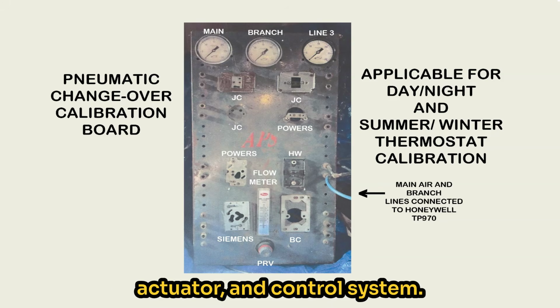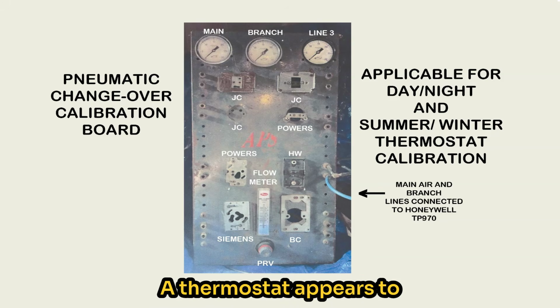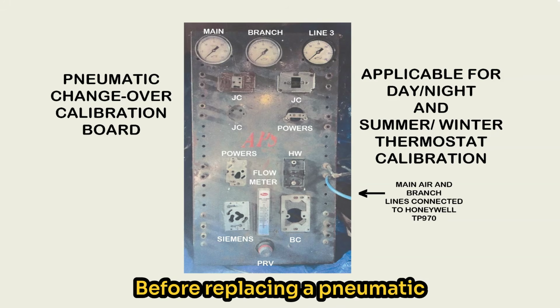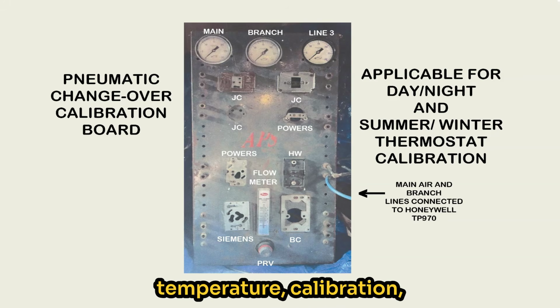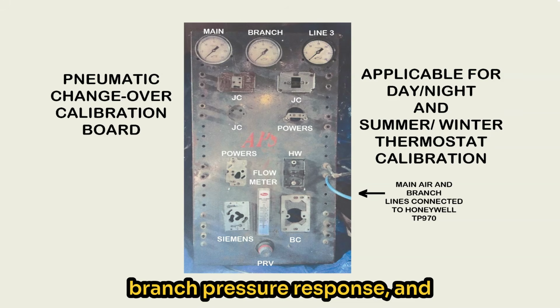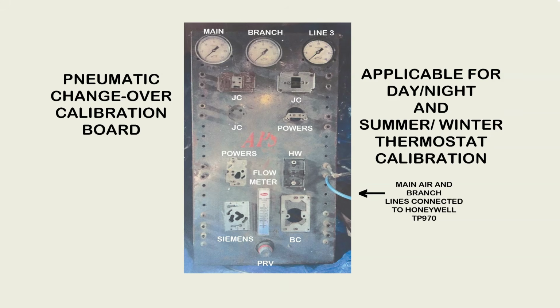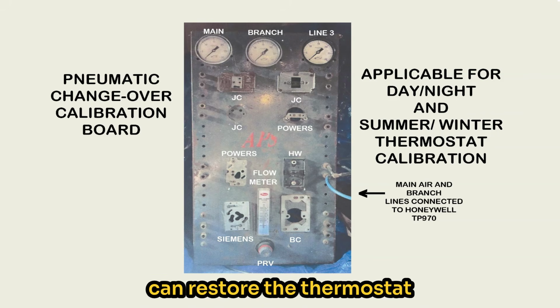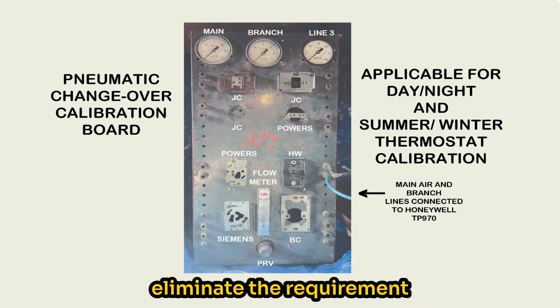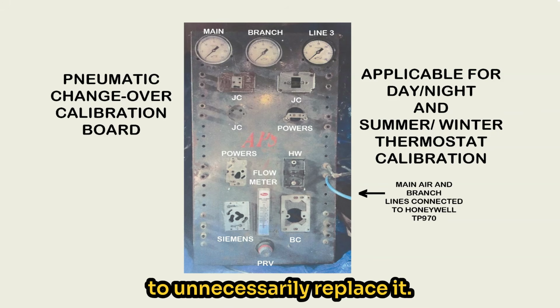actuator, and control system. A thermostat that appears to be defective may simply be out of calibration. Before replacing a pneumatic thermostat, verify its temperature, calibration, branch pressure response, and mode changeover pressure. In many cases, proper calibration can restore the thermostat to reliable operation and eliminate the requirement to unnecessarily replace it.